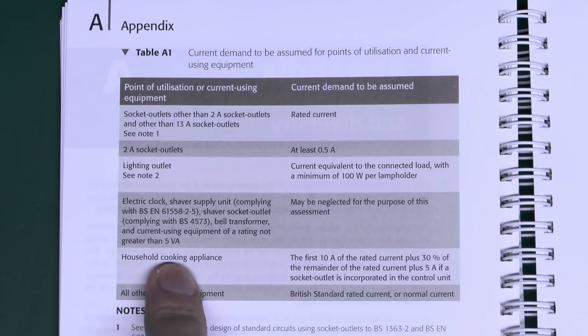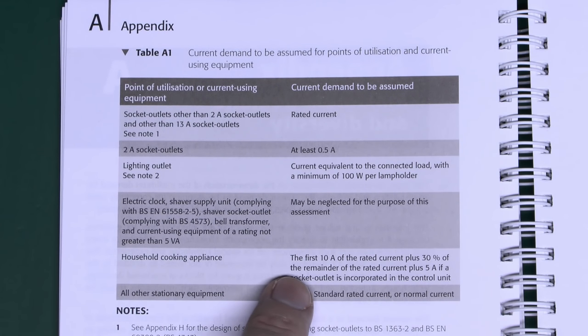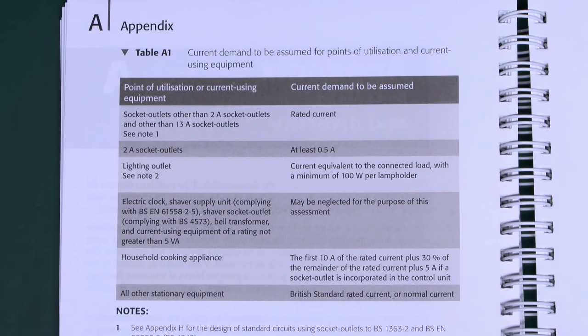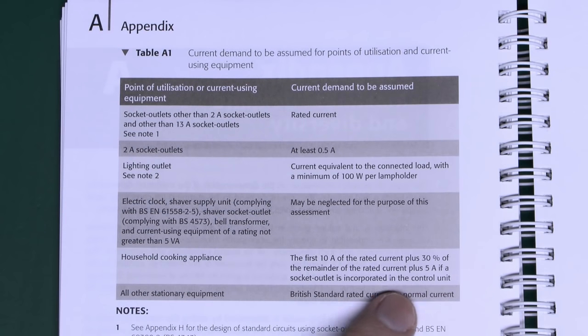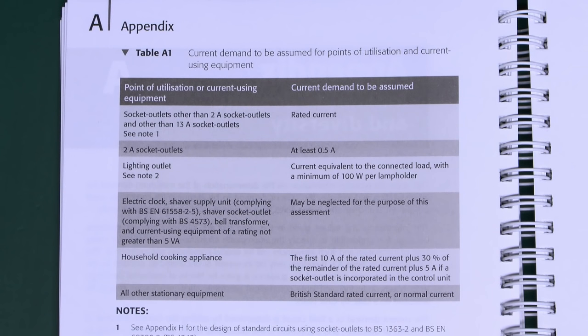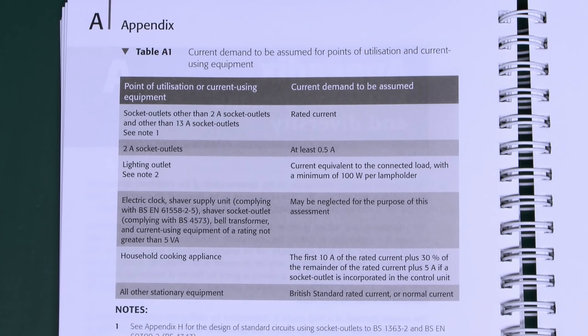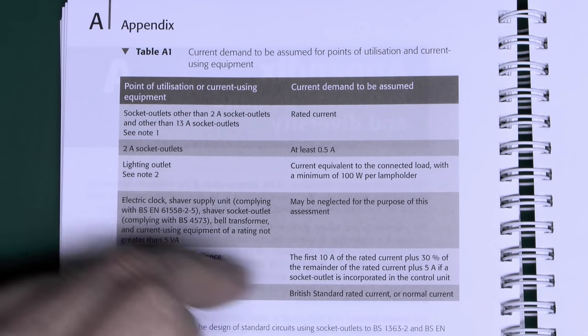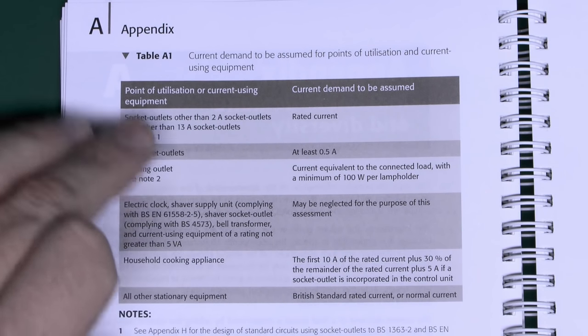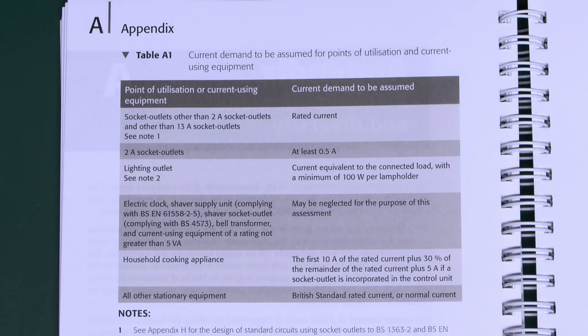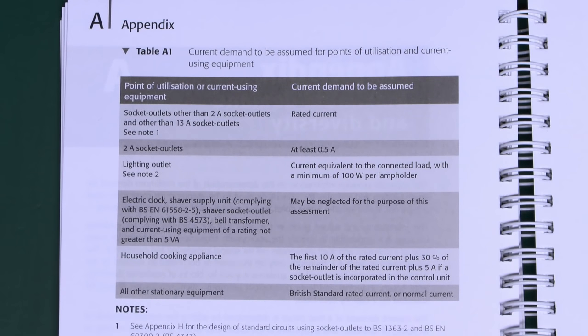For a cooking appliance — a freestanding cooker, or separate hob and oven — there's a specific formula: the first 10A, plus 30% of the remainder, plus an additional 5A if a socket outlet is included in the control unit. Everything else is either the rated current or normal current.